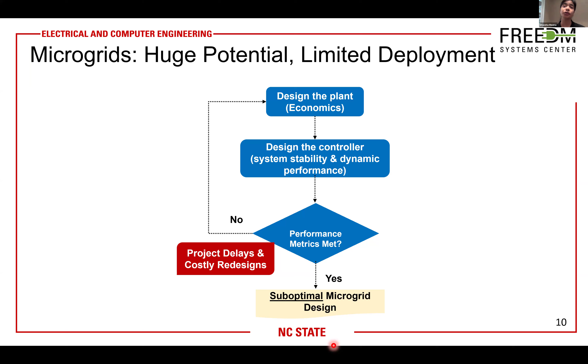A simple example is that the minimum cost design would be a microgrid with two synchronous generators, as they are cheaper compared to battery energy storage systems. But they experience rotor angle instability during faults and require fast-responding batteries that can provide voltage and frequency control. Hence, for optimal microgrid design, it's important to optimize both the plant and control simultaneously.